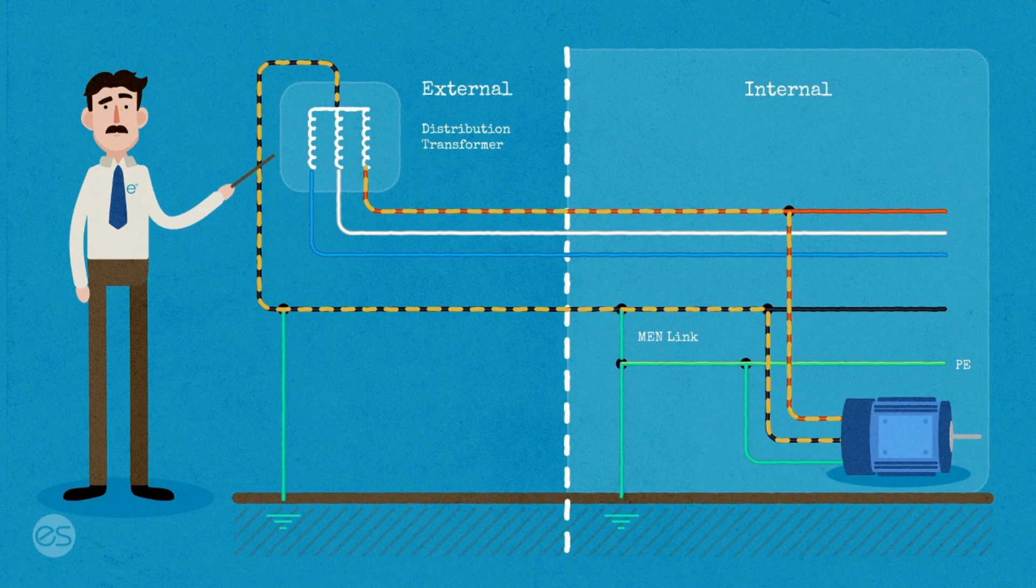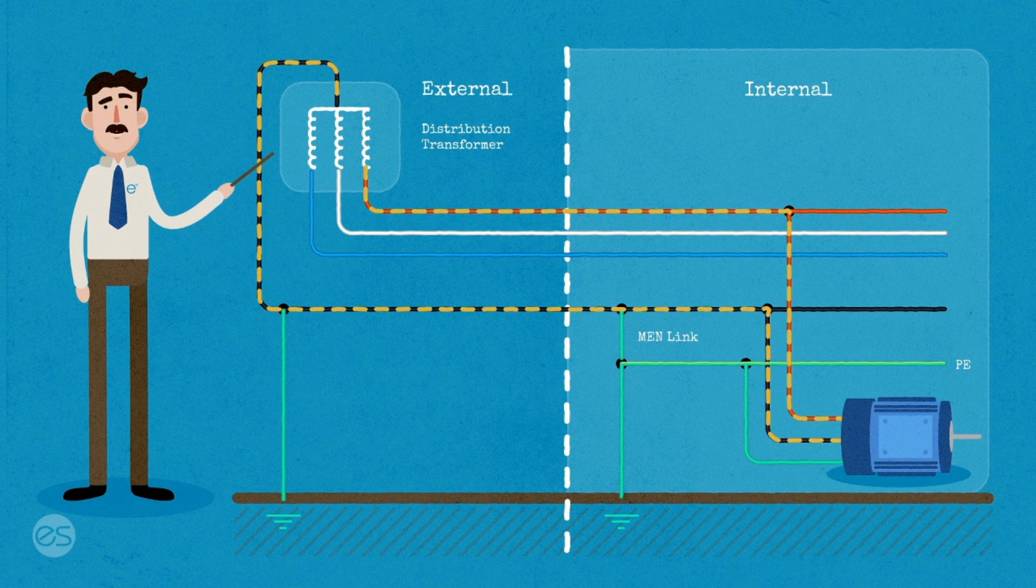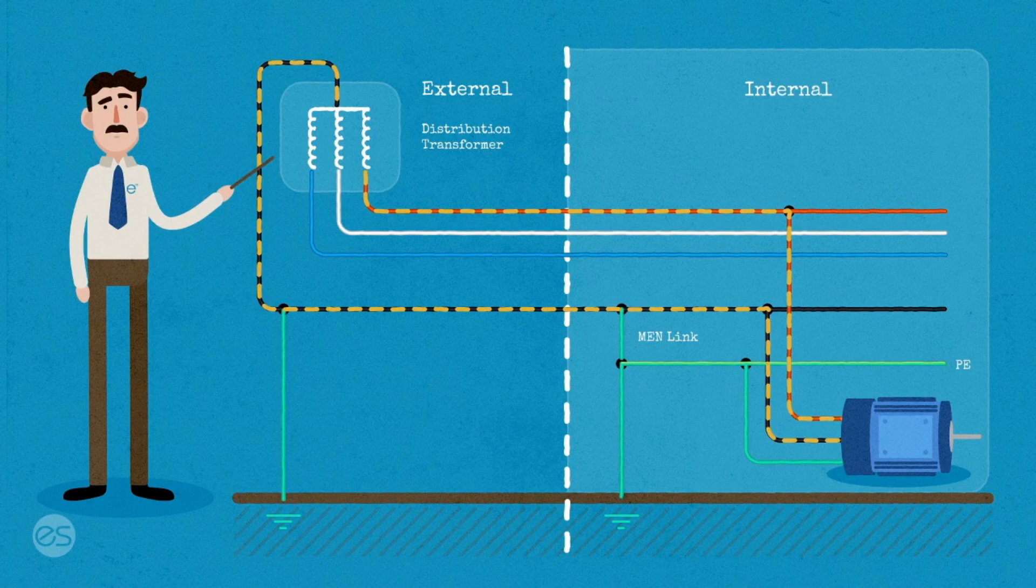Remember, our fault loop impedance path includes the supply authorities distribution transformer. So a special meter, called, funnily enough, a fault loop impedance meter, can be used to prove that our fault loop impedance is low enough to allow our circuit breaker to trip. And that's that!